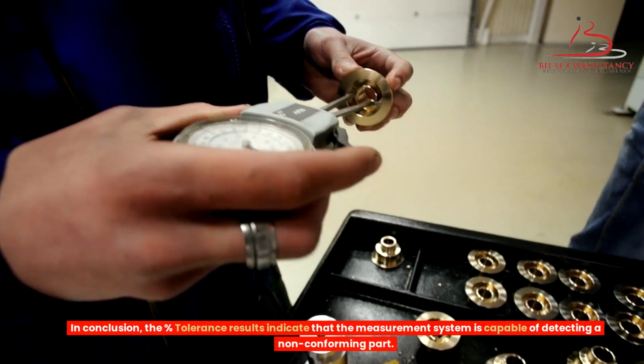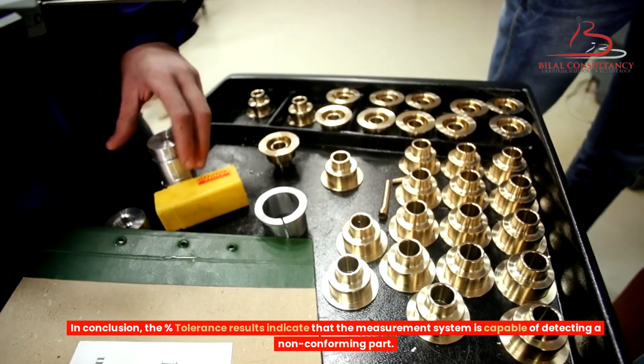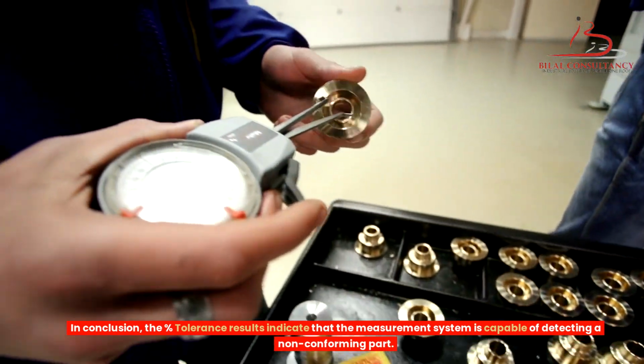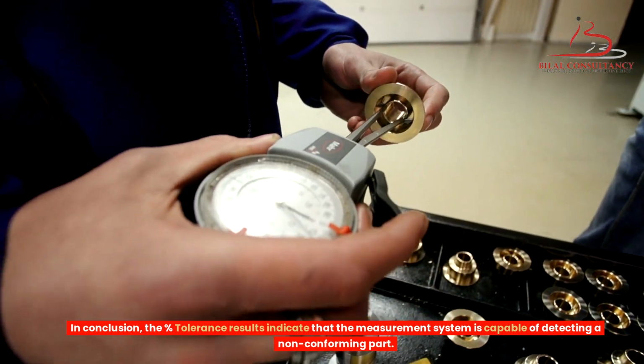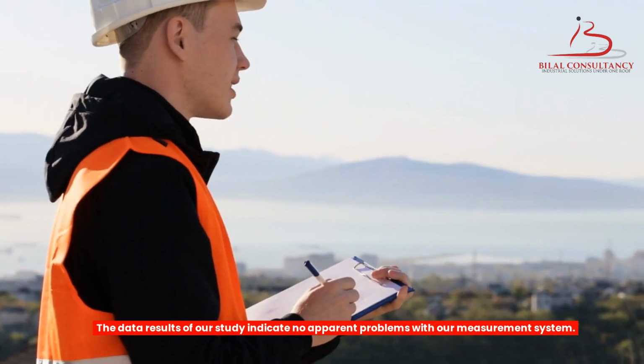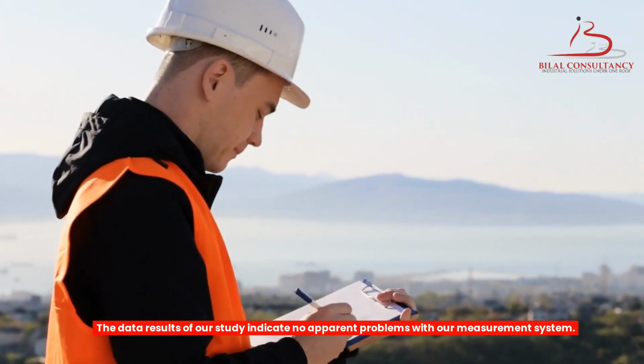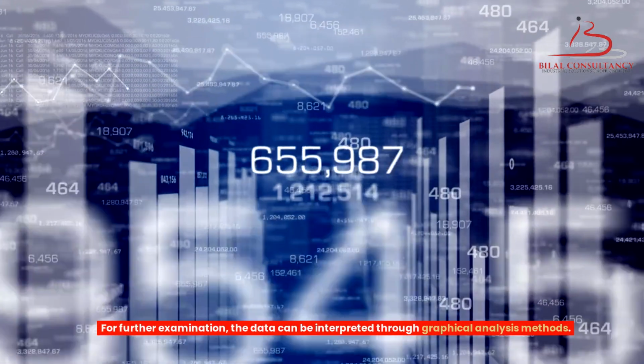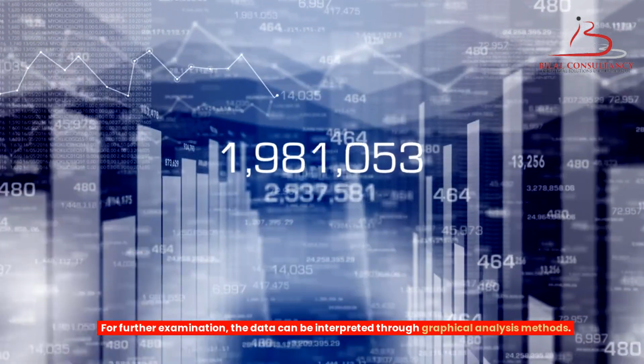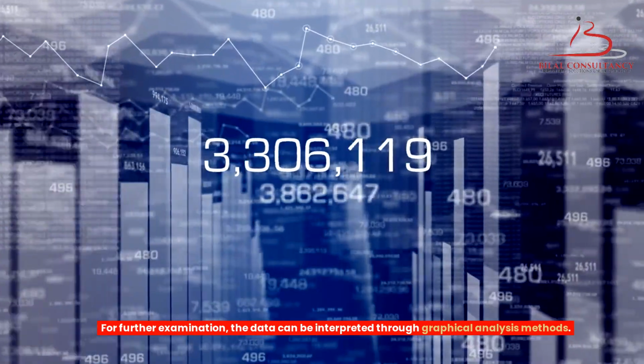In conclusion, the percent tolerance results indicate that the measurement system is capable of detecting a non-conforming part. The data results of our study indicate no apparent problems with our measurement system. For further examination, the data can be interpreted through graphical analysis methods.